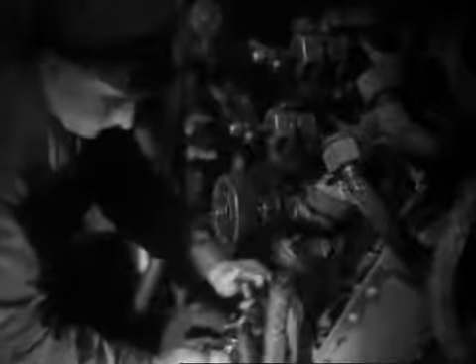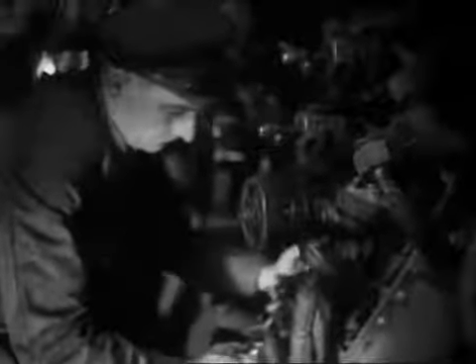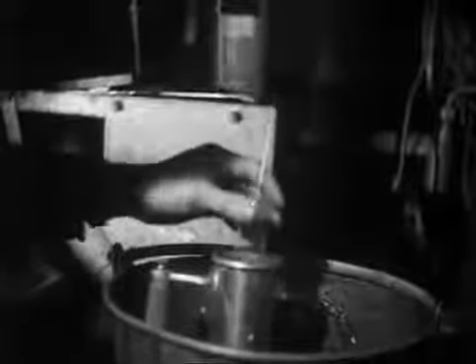You all know how a kettle furs up and gets scales inside it. That's due to impurities in the water. So frequent tests are made of the boiler water to ensure purity. Samples of water are drawn from the boiler into a hydrometer pot. The temperature is taken and the water is tested for density with a hydrometer.